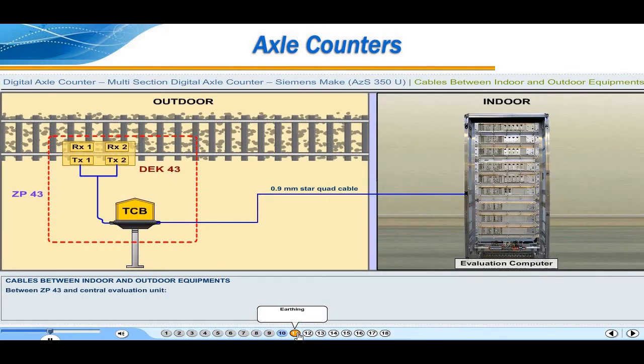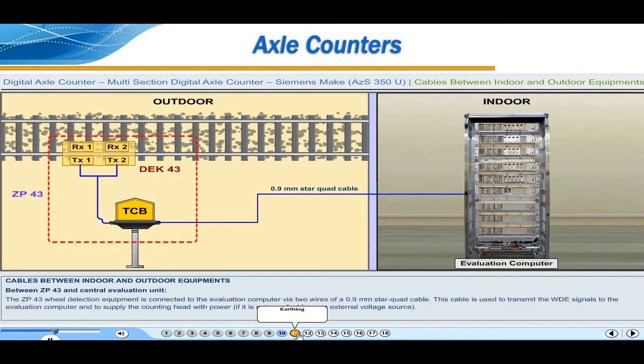Between EZP-43 and Central Evaluation Unit. The EZP-43 wheel detection equipment is connected to the evaluation computer via 2 wires of a 0.9 mm star quad cable. This cable is used to transmit the WDE signals to the evaluation computer and to supply the counting head with power, if it is not supplied from an external voltage source. Earthing. Earth resistance of the EZP-43 shall not be more than 1 ohm. For details, refer to topic 11, that is reference material.